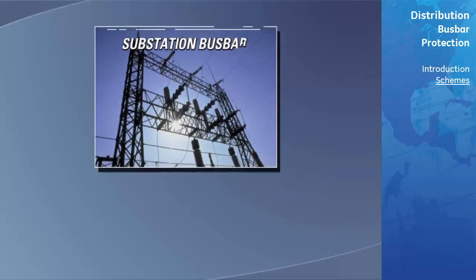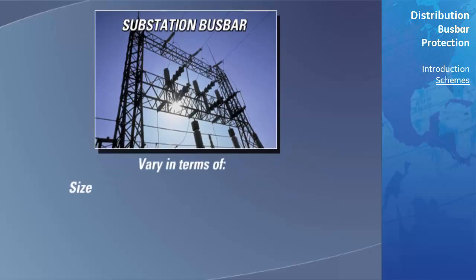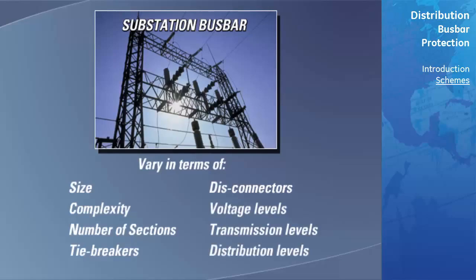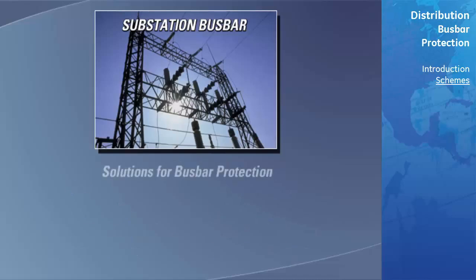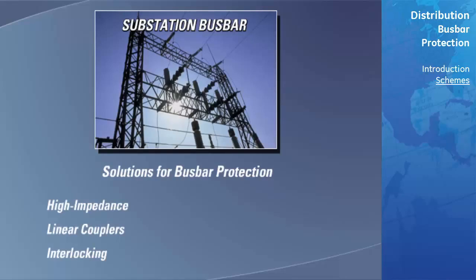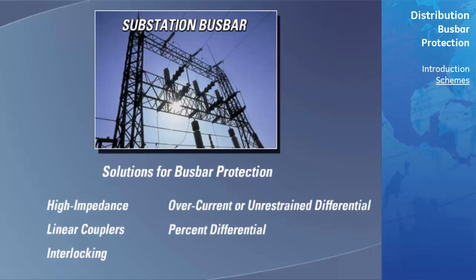Power system bus bars vary significantly in terms of their size, meaning the number of circuits connected, complexity, number of sections, tie breakers, disconnectors, voltage levels, transmission levels, and distribution levels. In the past, these technical aspects combined with economic factors led to a number of solutions for bus bar protection. The most common schemes are high impedance, linear couplers, interlocking, overcurrent or unrestrained differential, percent differential, and finally low impedance microprocessor based.